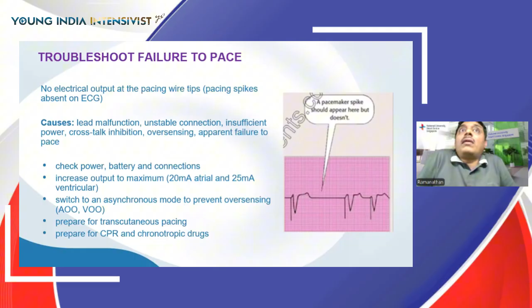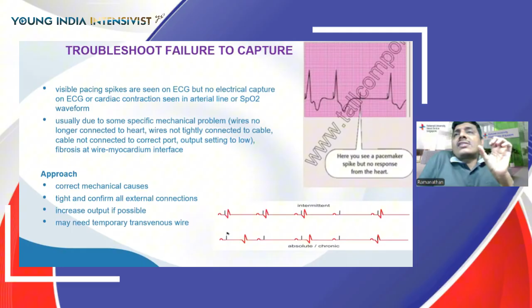And it's again usually a mechanical problem. Very often you get to see this when pacemakers are used for a longer time because the wire myocardium interface gets fibrosed. So again, the approach to this is essentially look for all these mechanical causes, make sure that all the external connections are well tight. And again, if nothing works, you might need a transvenous or a transcutaneous pacing mode.